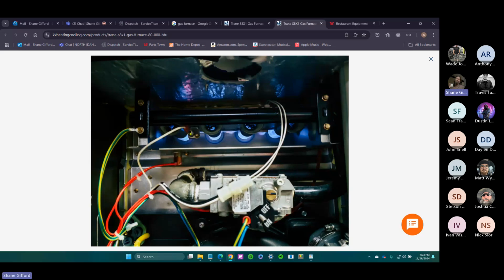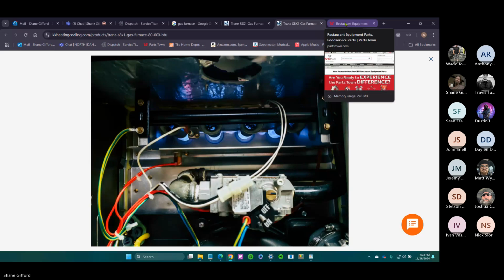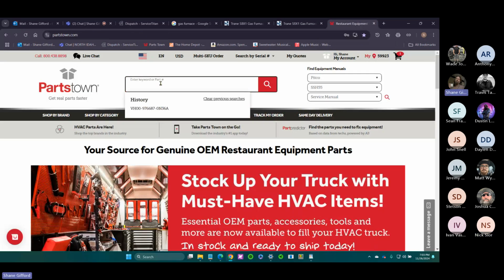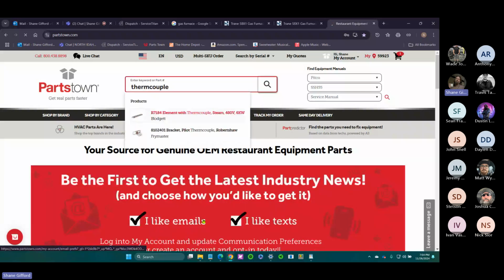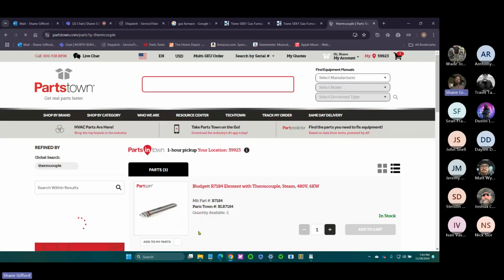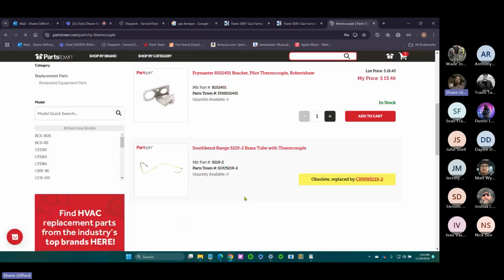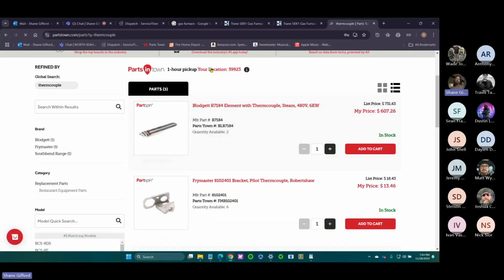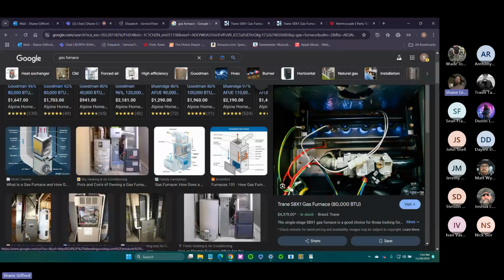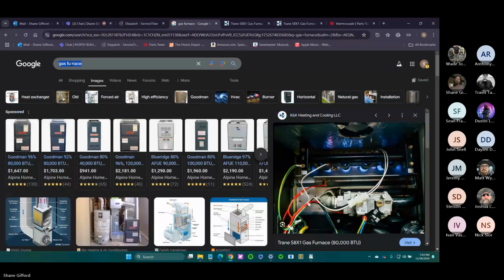either extremely low, where you can't control the pilot, like a gas pack or a gas furnace or something, or these things are coated in ceramic. That's because they have high voltage, and they coat them in ceramic so that it doesn't arc to the case that it's sitting in. Because if you have one that's arcing, that will immediately kill the circuit. Because that's telling the board, hey, we got a problem, shut off, no more flame.